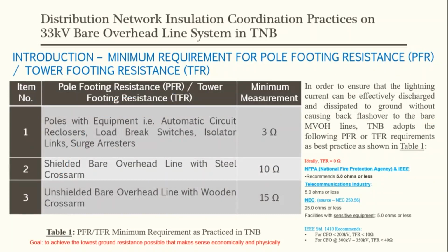shown in Table 1. Okay, for example, poles with equipment such as automatic circuit reclosers, load break switches, isolator links, surge arresters, the minimum requirement for the PFR would be 3 ohms. Shielded bare overhead line with steel cross arm, 10 ohms. And the unshielded bare overhead line with wooden cross arm, the minimum requirement should be 15 ohms.